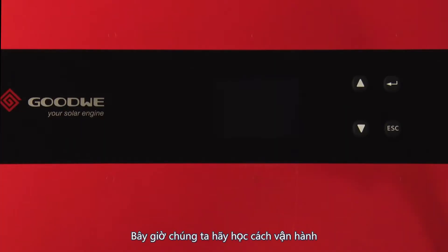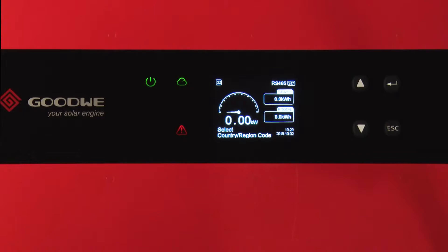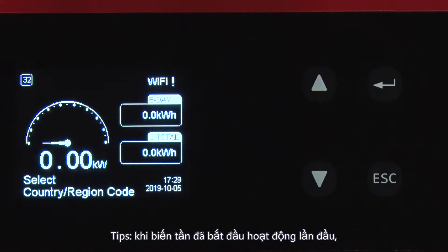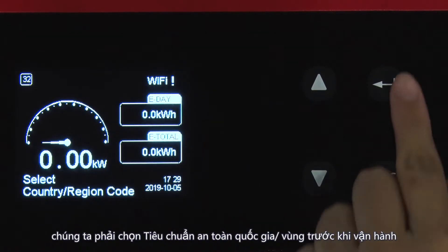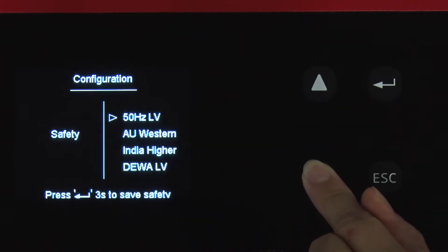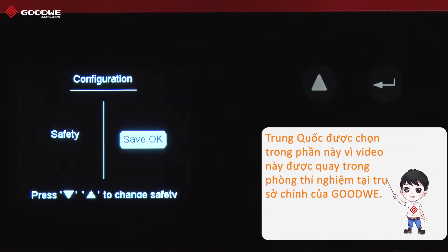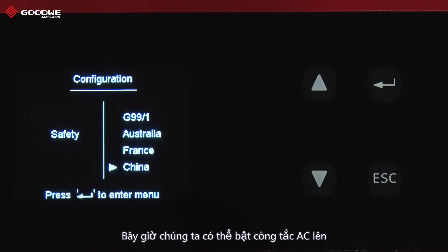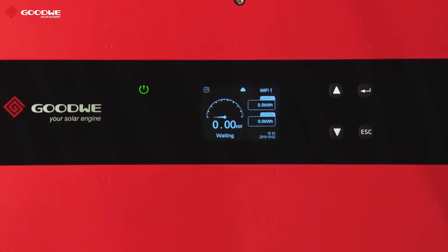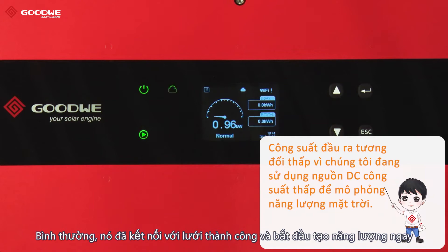Now let's learn how to do local commissioning. The DC switch was turned on and the system is starting right now. Tip: when the inverter is started for the first time, we have to select the safety country or region before any operation. Select the country and long-press Enter. Now we can turn on the AC switch. The inverter must go through self-checking before connecting to the grid. Now it has connected to the grid successfully and starts generating right now.